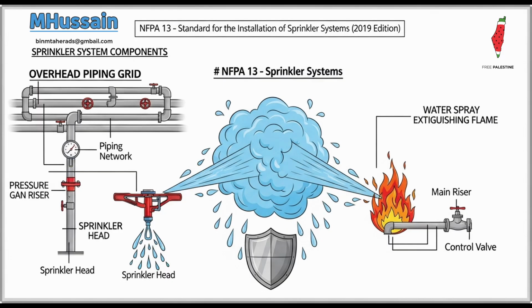Now, let's talk about what you called the Achilles heel of any sprinkler system, obstructions. A massive part of NFPA 13 is dedicated just to preventing anything from blocking that spray pattern. Absolutely. The ability of a sprinkler to develop its intended circular spray pattern is vital for control and suppression. And the standard is intensely prescriptive about preventing interference. The relationship between any potential obstruction and the sprinkler head itself is mapped out in really exacting detail.